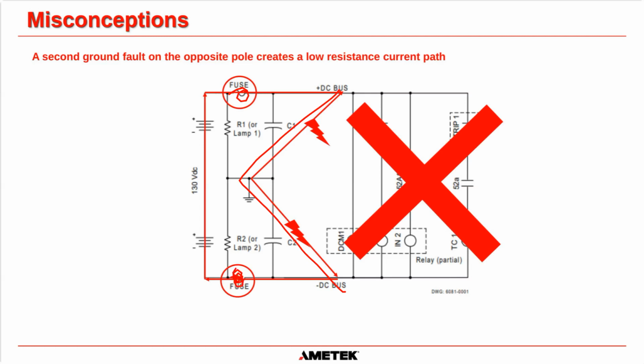And if one of those fuses blows, your breaker is not going to work anymore. So if it's an energize to trip, then you're not going to have the ability to trip that breaker anymore. And if it's a de-energize to trip, then basically as soon as you have both ground faults, it's going to de-energize and you are going to trip that breaker. Okay. So yes, one ground fault, that may not be the worst thing in the world, but two ground faults on the opposite pole, that is going to cause major issues in your plant.